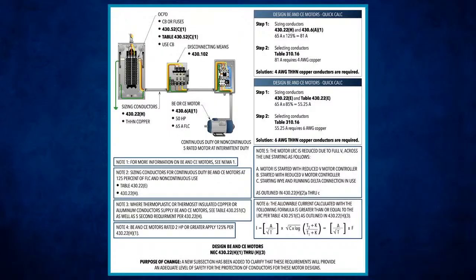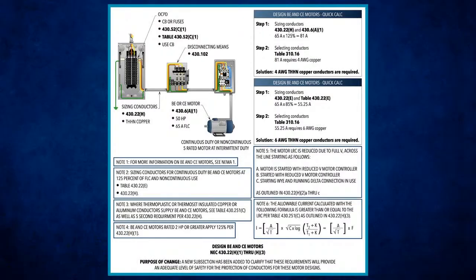And I'm going to do it like something you would see on a test. So let's say they ask you, "What?" I think you're having a hard time understanding what we're talking about, weed man, because nor are we saying that NEC limits you to 175%. Here's a good example. What percentage, Jeremy, if I look on an AC unit and they have a minimum and maximum size circuit breaker there, what percentage do you think they use to make that determination?